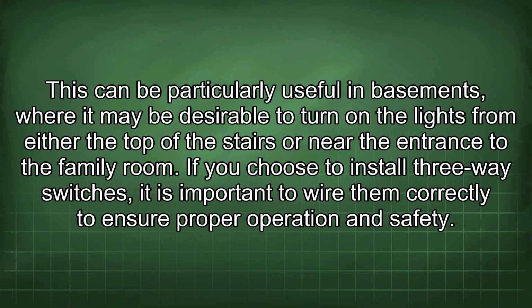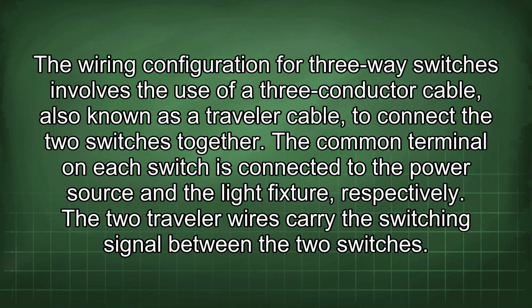If you choose to install 3-way switches, it is important to wire them correctly to ensure proper operation and safety. The wiring configuration for 3-way switches involves the use of a 3-conductor cable, also known as a traveler cable, to connect the 2 switches together. The common terminal on each switch is connected to the power source and the light fixture, respectively. The 2 traveler wires carry the switching signal between the 2 switches.